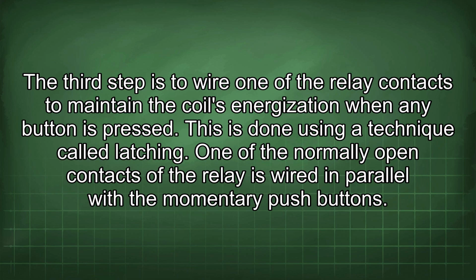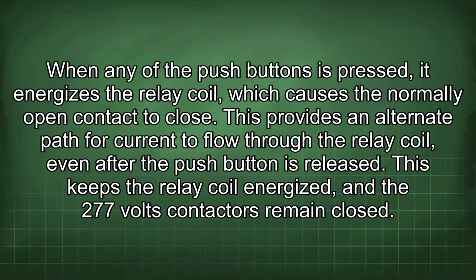One of the normally open contacts of the relay is wired in parallel with the momentary push buttons. When any of the push buttons is pressed, it energizes the relay coil, which causes the normally open contact to close. This provides an alternate path for current to flow through the relay coil, even after the push button is released. This keeps the relay coil energized, and the 277 volts contactors remain closed.